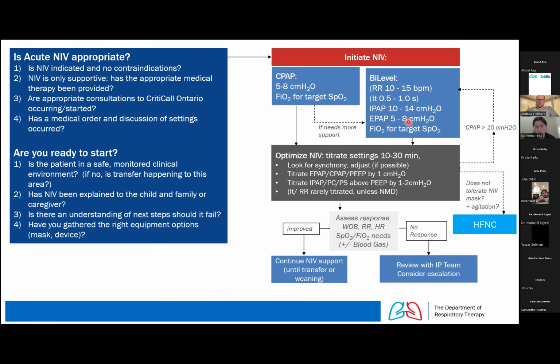Sorry, now I know why I'm looking at these numbers and saying they're really low. These are the starting settings that I would start with. And then if you optimize your NIV, you would augment from there, usually by 1 or 2. If you need more than 10 of CPAP, then you would probably look to transition to bi-level to give a bit more support.